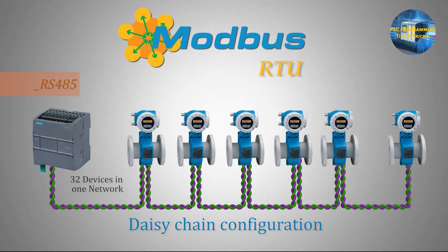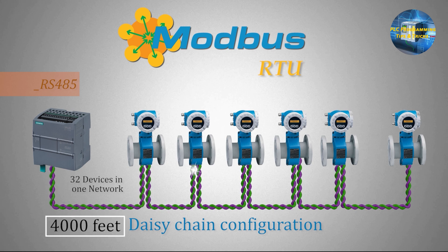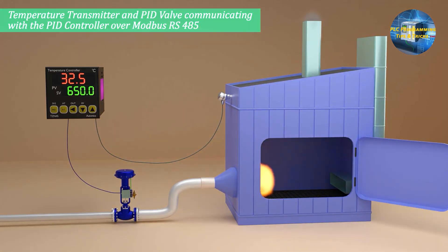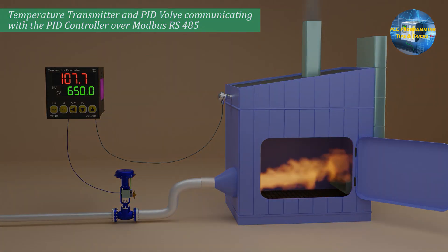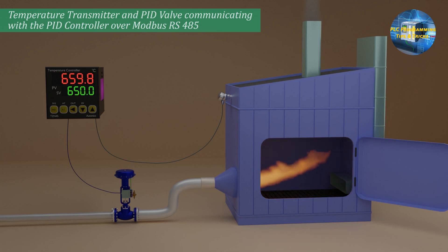Here's the key point: RS-485 is half-duplex, meaning communication can only go in one direction at a time. But it's still super reliable over long distances — sometimes up to 1200 meters or 4000 feet. In summary, Modbus RTU is used when devices need to communicate in harsh environments, like factories or plants, over long distances, and where reliability is more important than speed.